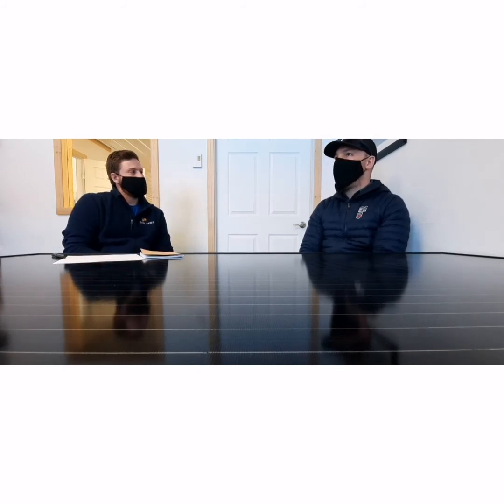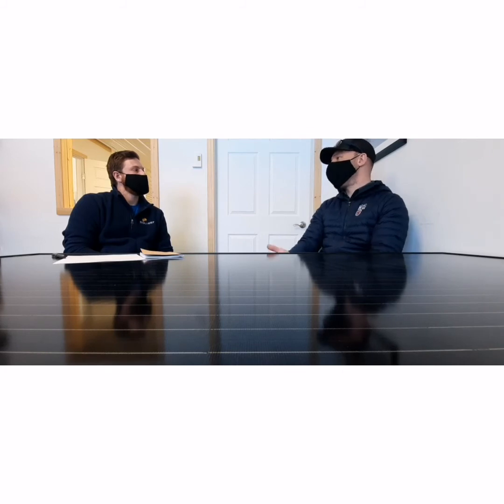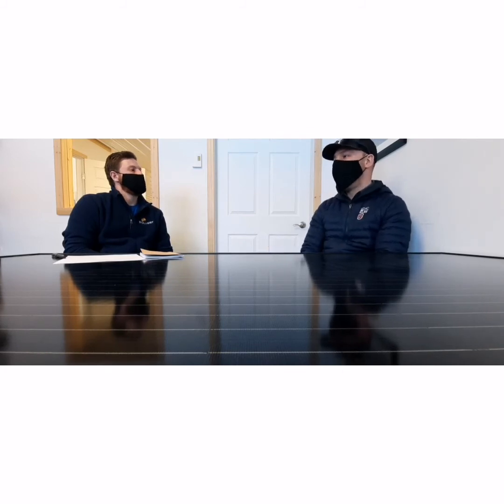Yeah, when we're operating a research station that's got minus 80 freezers, minus 40 freezers, we've got all the foodstuffs, the kitchen, the wash house, we've got scientific equipment, we've got a dryer or a washing machine, these things with these high peak draws. You have to size a generator as if they're all going to come on at the same time, which conceivably could happen. But with the battery bank, we can manage that whilst also not having to run the generator full time. So yeah, the battery bank was a huge win, I think, for the station.